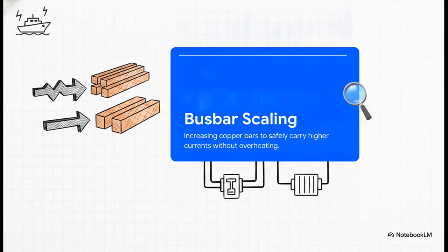Okay, so how do we actually apply this to technical sizing? Well, that main bus bar compartment we just mentioned is definitely not a one-size-fits-all situation. The industry uses a practice called bus bar scaling. This basically means that the number of physical copper bars and their actual cross-section scales directly with the rated current the board is built to handle. Simply put, more current means you absolutely need more physical copper to carry it so things don't overheat.